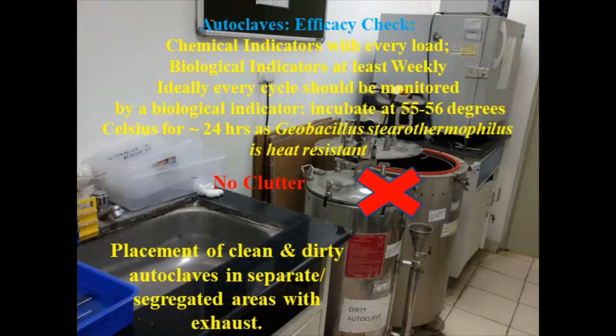In the presence of media, if the spores are still viable, they will germinate. And after germination, due to a biochemical reaction, the color of the media will change from violet or purple to yellow within 24 hours. So if after incubation we find that there is a color change, then the autoclave was not acting effectively. The autoclave didn't achieve the temperature of 121 degrees Celsius, which could have killed the spores, so the spores have remained viable. A color change indicates that the autoclave has to be serviced or changed, which calls for an intervention on the part of the autoclave user. But if there is no color change after 24 hours of incubation, the autoclave cycle was effective.